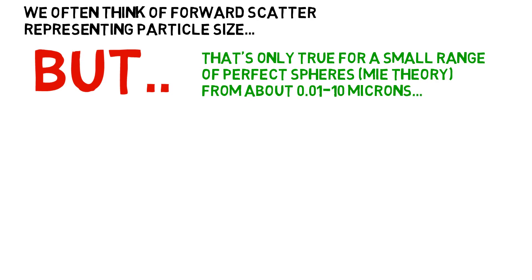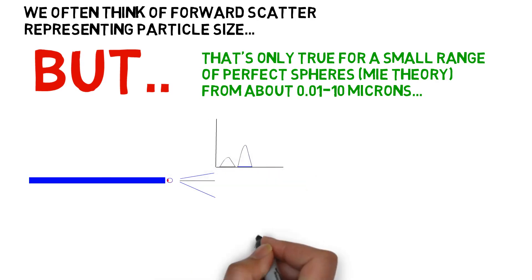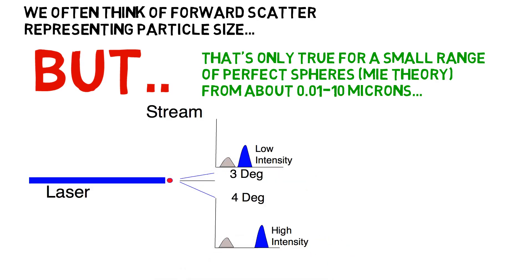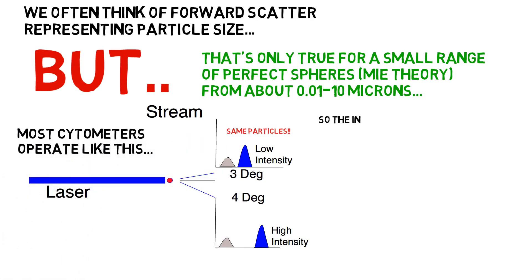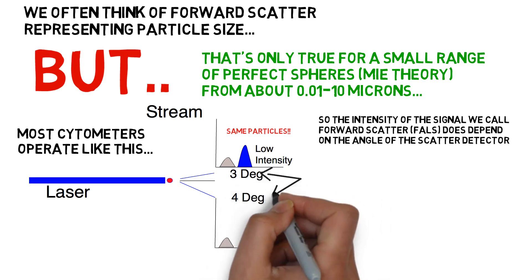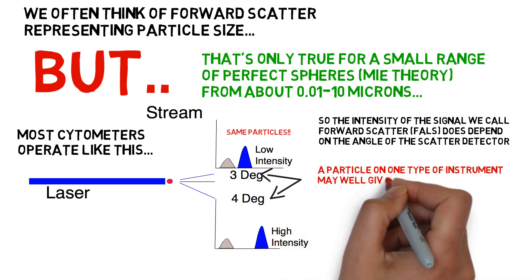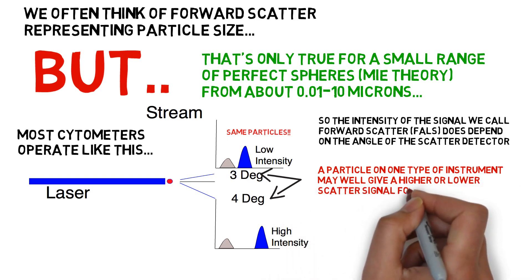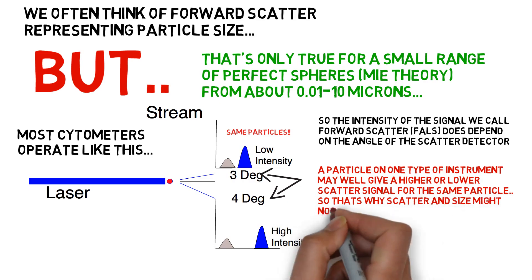When you look at this diagram of how we measure FALS, you can see that the intensity of the signal is dependent on the angle of the forward detector. The 3-degree signal can differ from the 4-degree signal, showing how the angle can make a big difference in signal intensity. Different instruments have different angles of light scatter, which is why they don't all measure particles the same way. This means you often can't compare scatter plots from one brand of instrument to another.